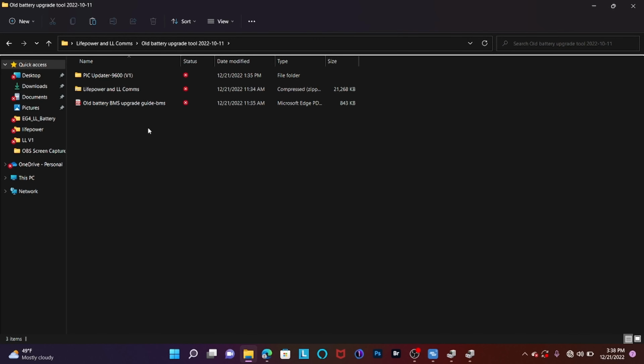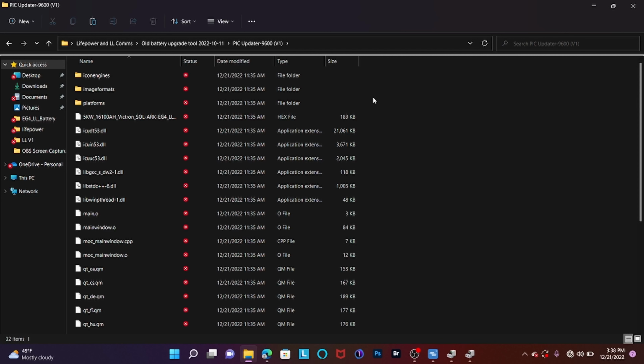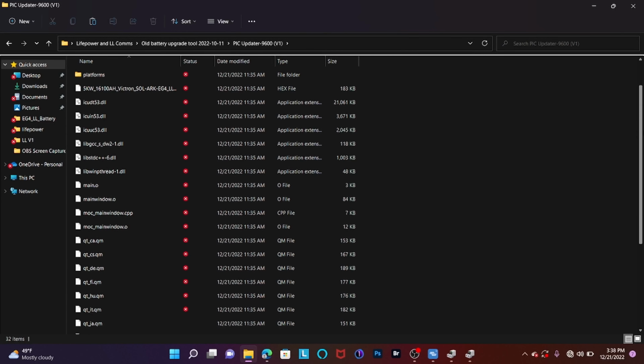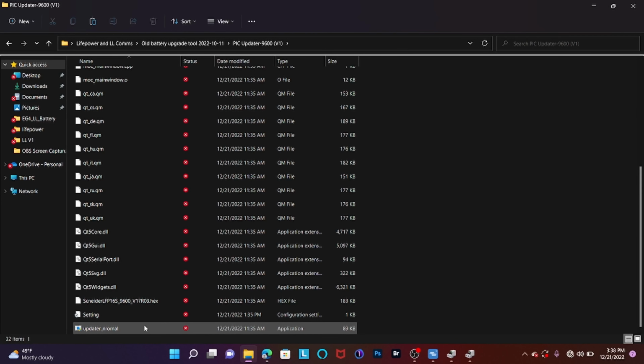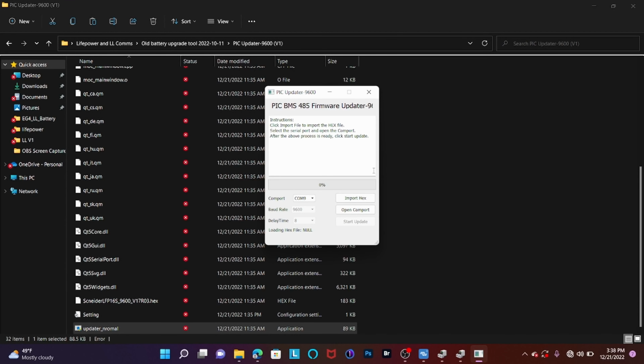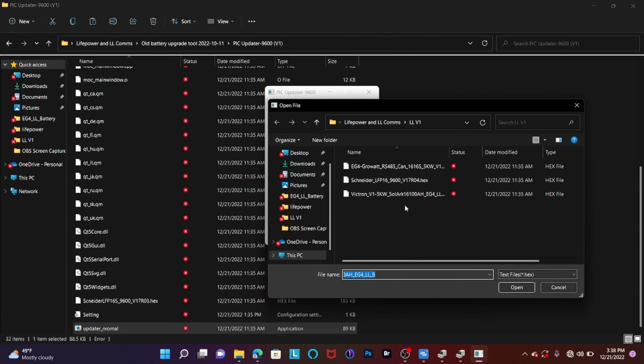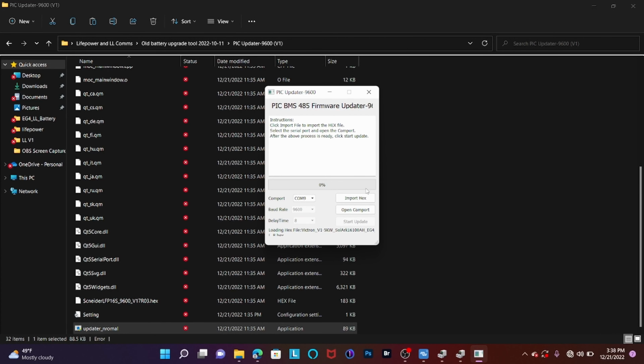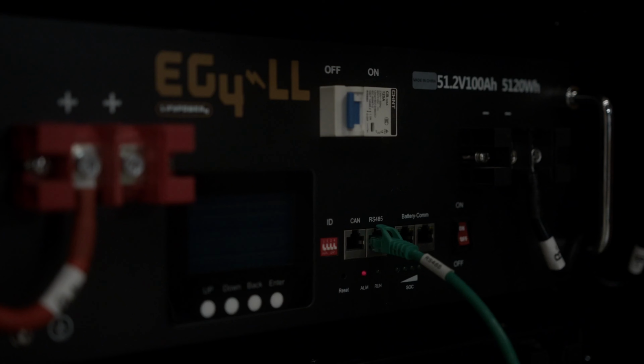We're going to open this file, and we're going to scroll down until we find the update application. So that we know that our COM port 9 is correct, let's go ahead and import our firmware. Now, which firmware you use depends on which inverter you use. Today we're doing a Victron. Now we're going to open our COM port and we're going to send the update. The alarm light will come on during this update.